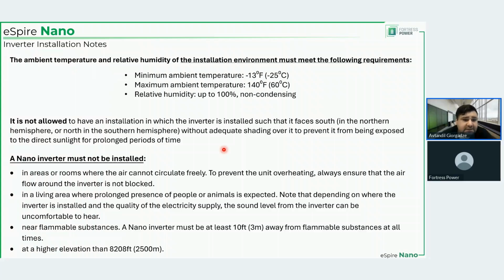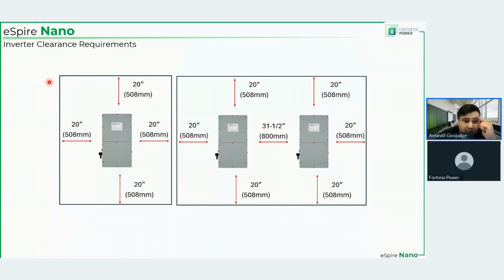Near flammable substances, the nano inverter must be at least 10 feet away from anything flammable, which is understandable. And at a higher elevation than 8,208 feet, 2,500 meters, although it says that it must not be installed there, it can be installed there, but in that case, we will need to do the derating ourselves, in a way that the customer cannot change. So the clearance requirements for the inverters, and again, this is for the inverters alone, are given right here. Again, I'm not going to get into every single number here. At the end of the presentation, you will get the PDF of the presentation that I'm going through.